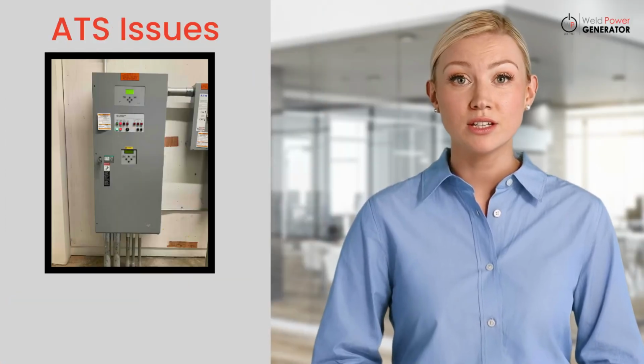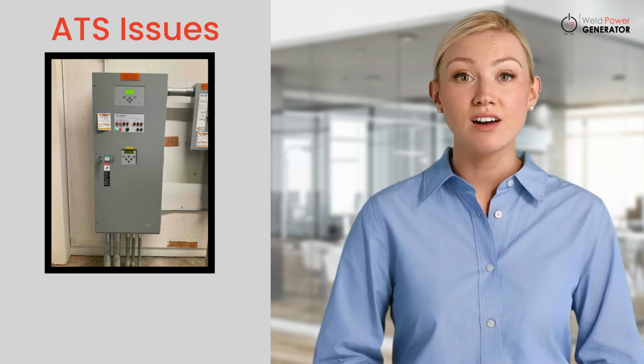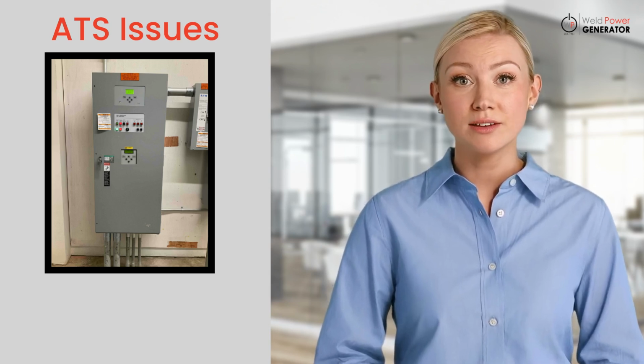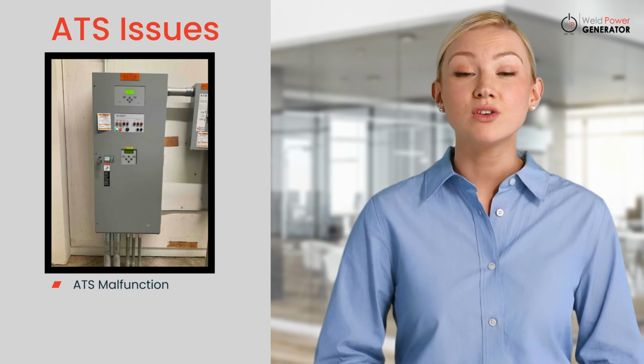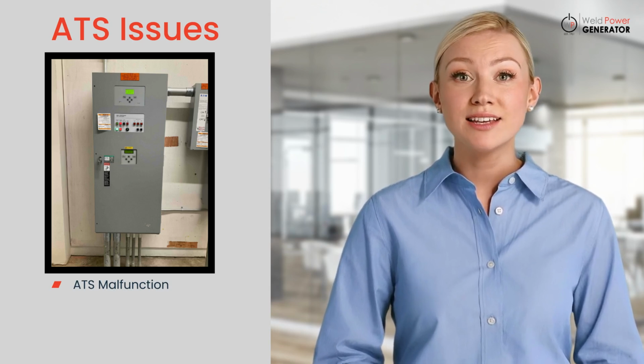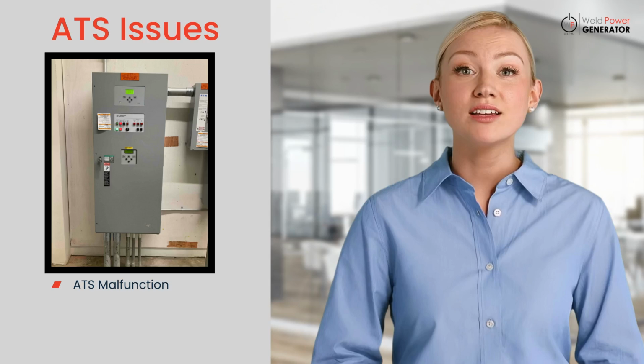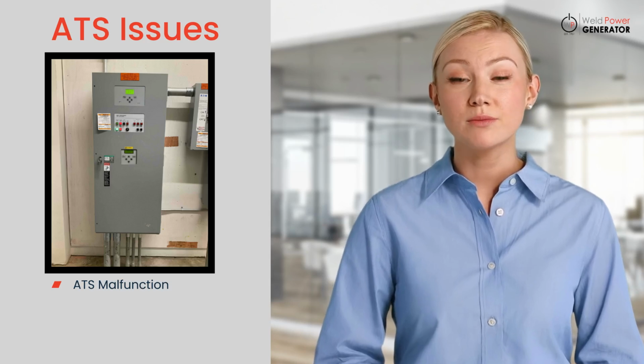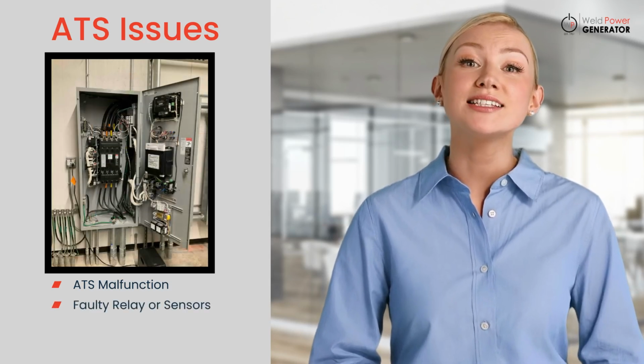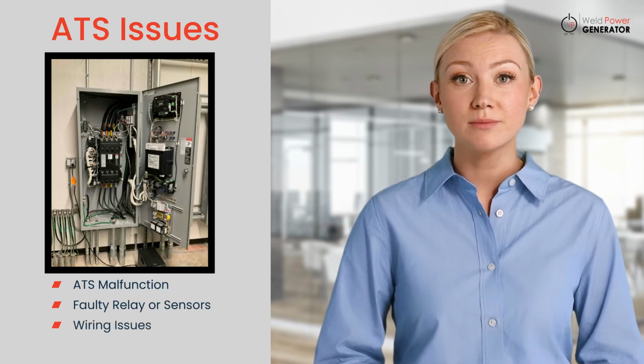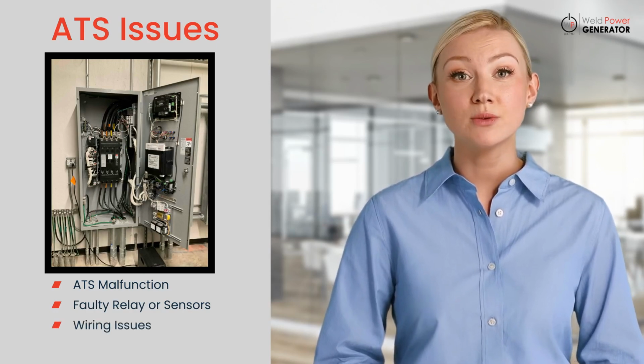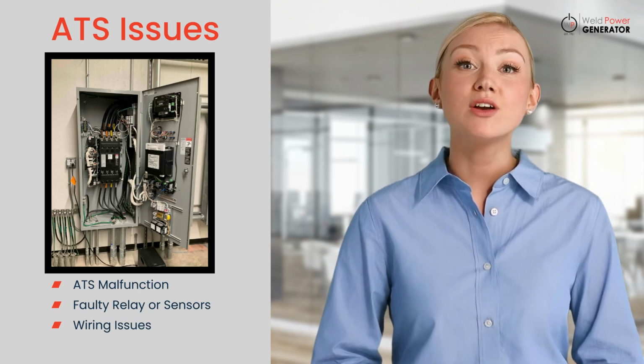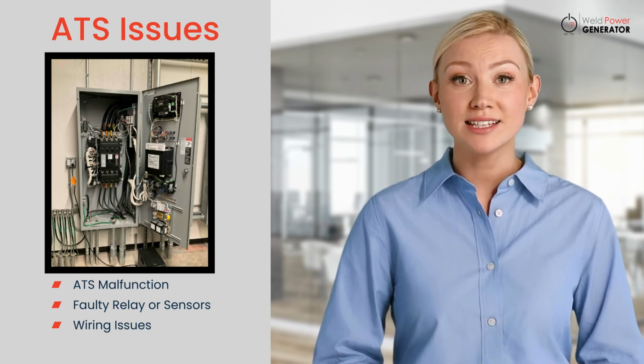Automatic transfer switches play a critical role in sensing power loss and directing the load to the generator. If the ATS malfunctions or misinterprets power availability, it may signal the generator to start even when utility power is stable. This could be due to a faulty relay, sensor issues, or improper wiring. Diagnosing the ATS with a professional technician can determine if repairs or replacements are necessary.